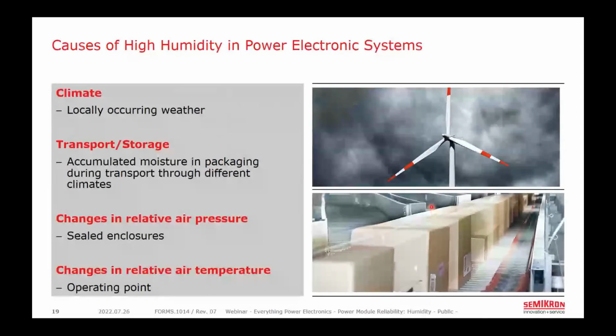Transport and storage of equipment in such regions can trap moisture inside equipment. For example, if it's partially wrapped in plastic and warm, humid air gets inside, and then the moisture condenses into a liquid once the unit is moved to a cooler location. Or consider the process of water molecules diffusing into the silicone gel inside the power module that we described earlier. A power module sitting in a humid environment may have these water molecules move into the silicone gel, and it takes some time, and perhaps some thermal motivation, to move those molecules out of the power module once it gets to a drier location.